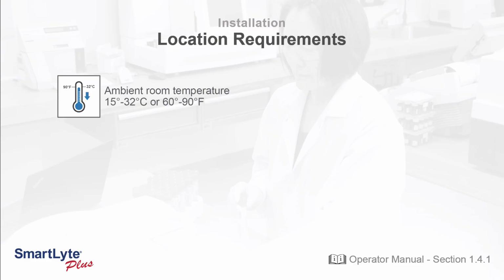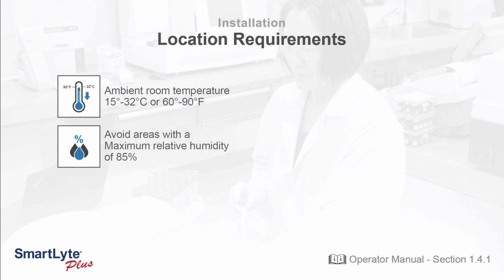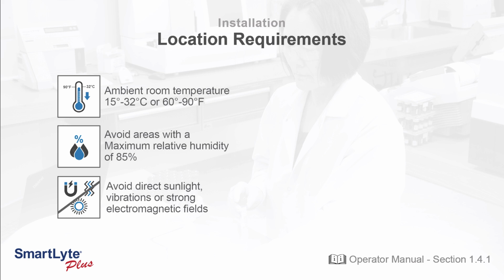You want the ambient room temperature to be between 15 to 32 degrees Celsius or 60 to 90 degrees Fahrenheit, and avoid areas with a maximum relative humidity of 85%. Make sure the unit will not be exposed to direct sunlight, vibrations, or strong electromagnetic fields, such as electric motors, transformers, X-ray equipment, and cellular phones.